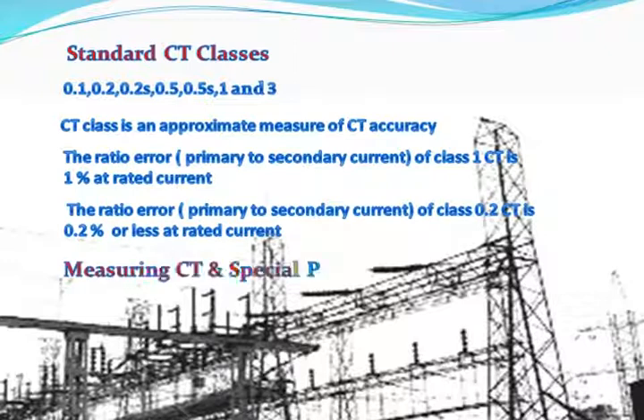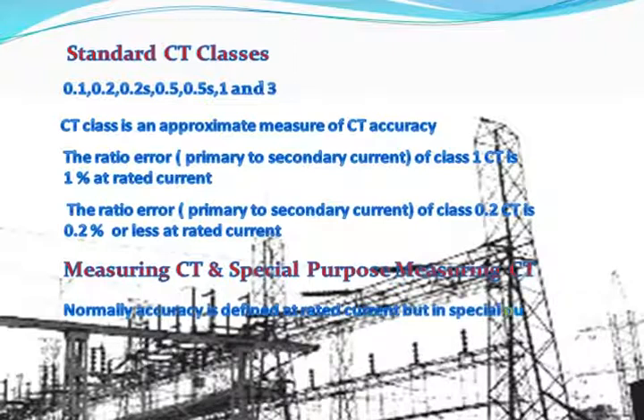Difference between measuring CT and special purpose measuring CT: normally accuracy is defined at rated current, but in special purpose CT, accuracy is defined at 20% of rated current.